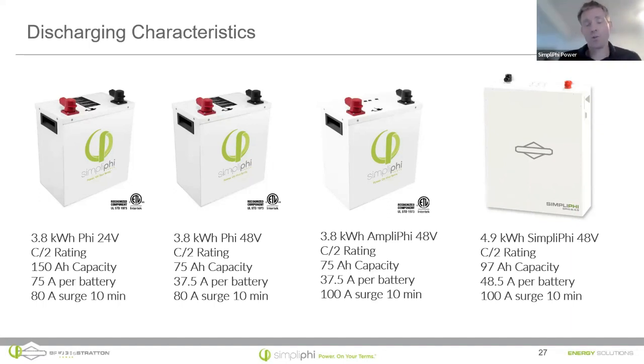So if we discharge to only 10% of the battery's capacity remaining, we drop down from 10,000 cycles to closer to 5,000 cycles. That's still 13 years if cycled once a day, but that's a big difference. And if we discharge to 100% depth of discharge, take the batteries all the way down to 48 volts, then we're looking at only about 3,000 to 4,000 cycles.